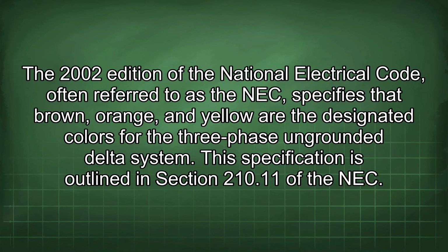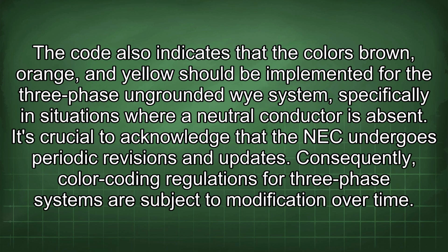The 2002 edition of the National Electrical Code, often referred to as the NEC, specifies that brown, orange, and yellow are the designated colors for the three-phase ungrounded delta system. This is outlined in section 210.11 of the NEC. The code also indicates that brown, orange, and yellow should be used for the three-phase ungrounded Y system, specifically where a neutral conductor is absent.